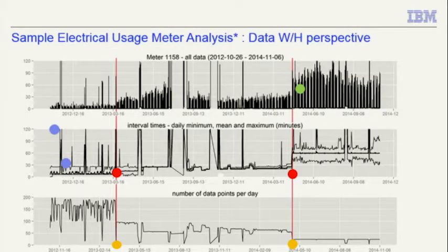But when you have a lot of sensors, you have a lot of infrastructure, you may not be reporting every 15 minutes. You might get some problems in the network, and the sensor might go down and so on. So if you actually look at this data here, you can see that the intervals between them correlate directly with these spikes that we have in the data. So we can see that when there's a bigger gap in the sampling time, it looks like the energy has gone up.